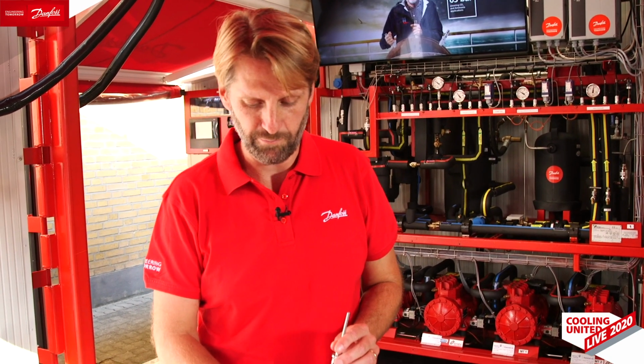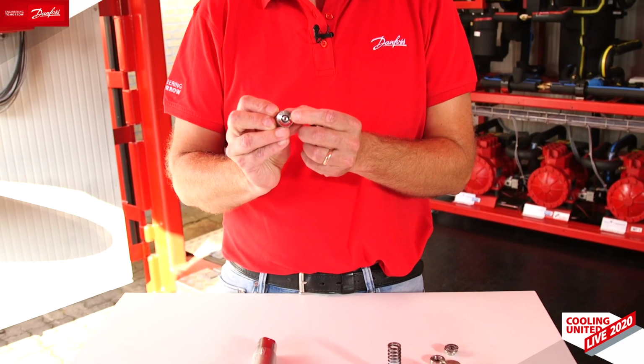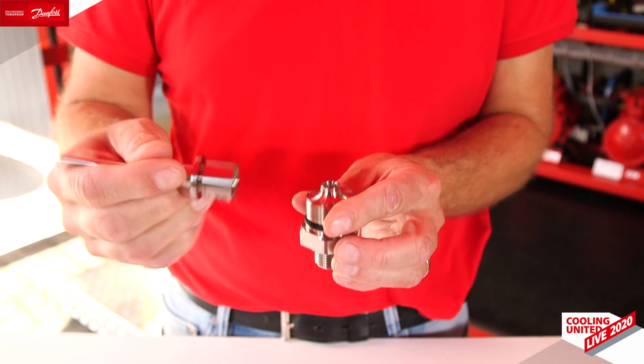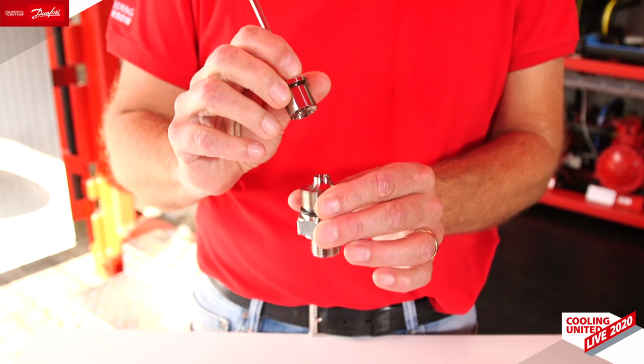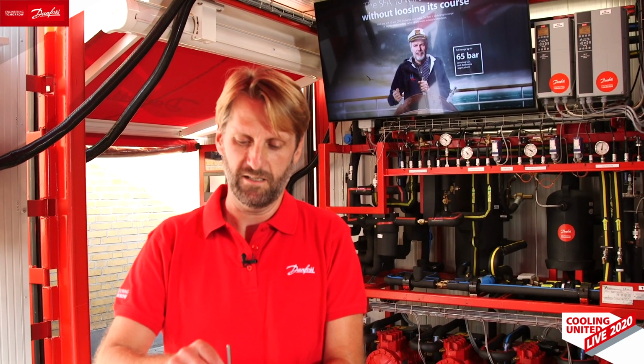Finally, you want to have a perfect reseating once you have the product relieving, which is quite common in CO2 systems due to the nature of CO2 and standstill. You want a perfect reseating. Again, the O-ring here will help us a lot, because you can have a little impurity coming from the system, and the product is actually capable of taking, at least to some extent, these particles and still ensure a tight seating.